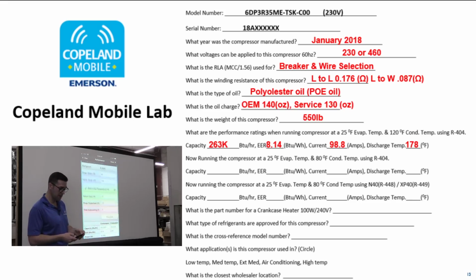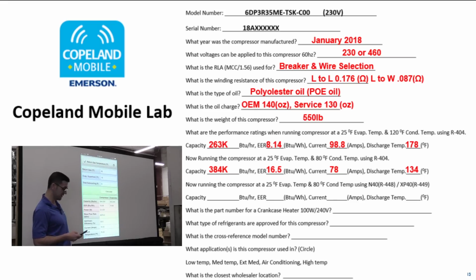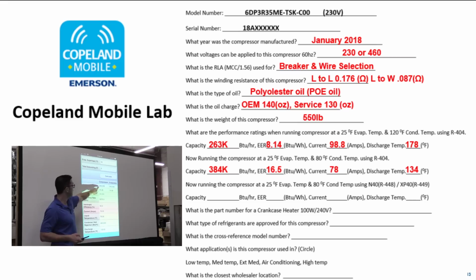If I just go back up here and change this 120 to 80, changing the compression ratio, press calculate. Now look at this compressor. 384,000 BTUs this compressor can do now at the different design conditions. And look at the amps, only 78 amps. So I'm getting more capacity using less work, 78 amps. That's something to really think about, especially when you're doing optimization projects. Is everybody okay with that right now?